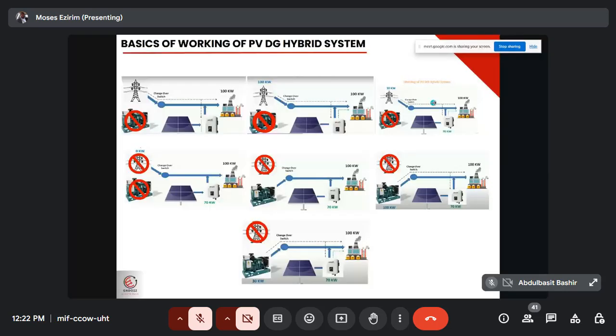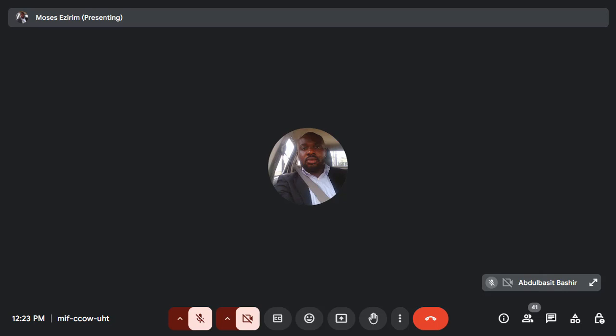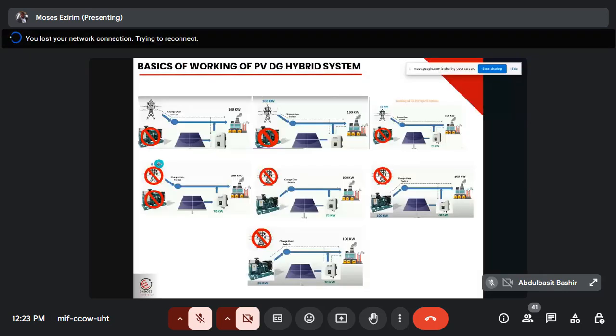Now, let me tell you this. The inverter does not automatically start producing. It has to synchronize. What I mean by synchronization, which I've explained, is that the voltage must match that of the grid. There will be blackouts because the inverter is not synchronized. There is no reference from these two. There is no grid availability. The generator will not come up automatically, so there will be a blackout within this factory.